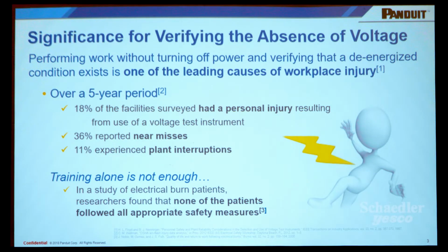What's the significance of an AVT? Basically, it does the live, dead, live test for you. It automates the traditional live, dead, live test. So OSHA says that lockout tagout is the second most willfully violated procedure on plant floors. So a lot of injuries and a lot of citations occur from skipping a lot of the de-energizing steps required to service a machine. Absence of voltage testers take out that human error step. They're permanently mounted in the enclosure. It reduces chance of human error or just willful neglect of taking the steps to properly de-energize and properly test for de-energization of the system.